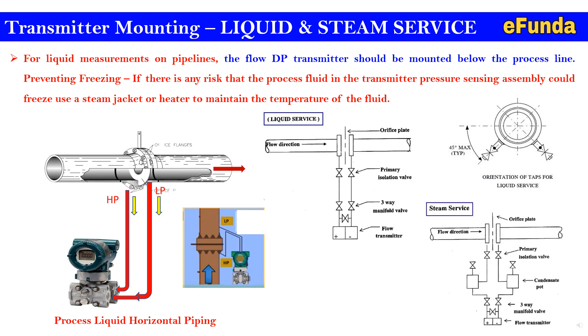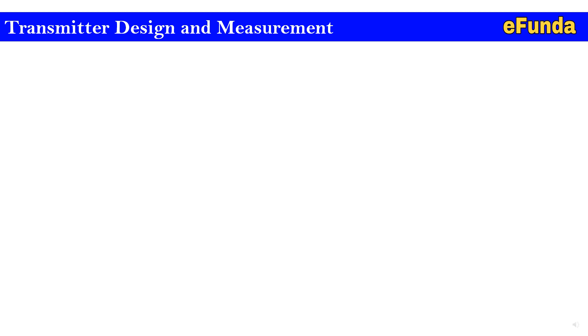For steam service, a similar type of hookup is used as per liquid service. The only difference is that condensation pots will be added at the same level where the tappings are connected. This ensures that condensates settle into the condensate pot, and the impulse line will always remain pressurized so as to have accurate steam measurement.